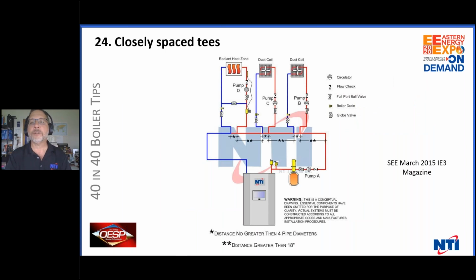Here we have a boiler that's on the primary loop. Circulator for the boiler circulates around the loop, and when it gets to each one of those T's, it doesn't get anywhere close to it. Isn't that great? Yeah, the 2 closely spaced T's is because the water in that main loop can't sense a pressure difference, so it won't flow to that zone unless the circulator comes on.